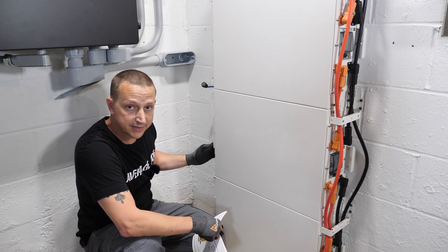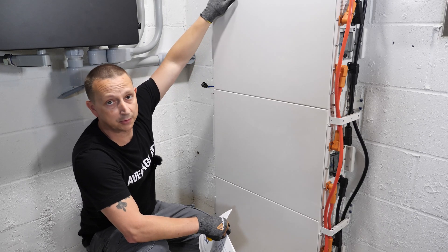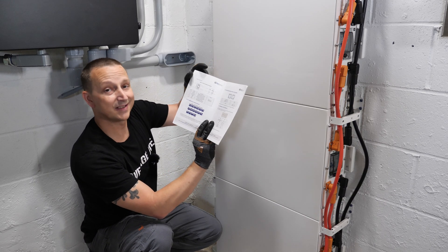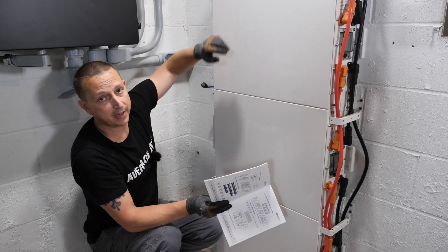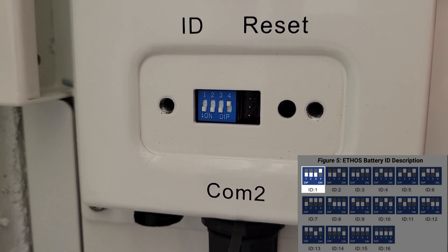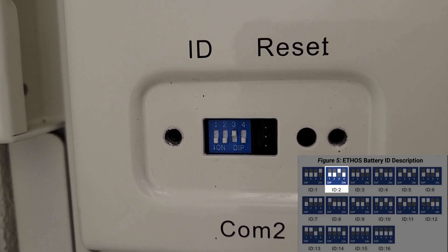Next we remove the little cover plates over the DIP switches so we can assign each battery a location or address to communicate with the controller box, which communicates with the inverter. In the Ethos battery manual — page 15 on mine — it shows how to set each ID. The battery closest to the controller box is battery number one. On battery one the first three switches are down and the fourth is up; on battery two the first two are down, third is up, fourth is down; on battery three the first two are down and the last two are up.